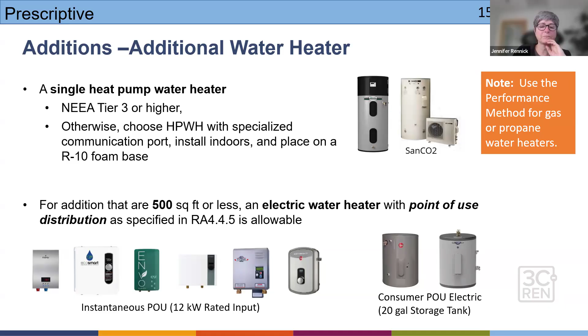And this is a plan check item, meaning the architects should show the distance from that water heater to their hot water plumbed fixtures, because then from the reference appendices, table RA 4.4.5, it tells you how much length of pipe in plan view you're allowed to have based on the diameter size of your piping. And then just FYI, the showers, you're going to use 1/2 inch, your sinks, 3/8 inch. And this would be shown on the plan.